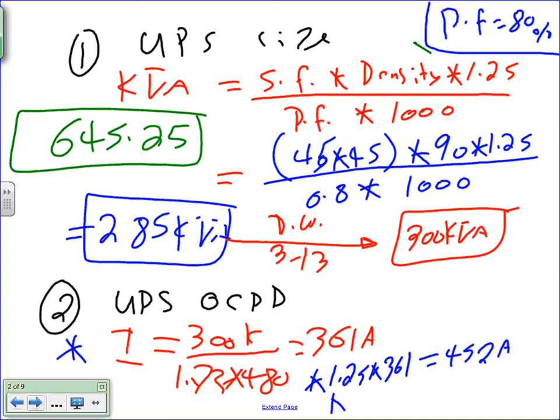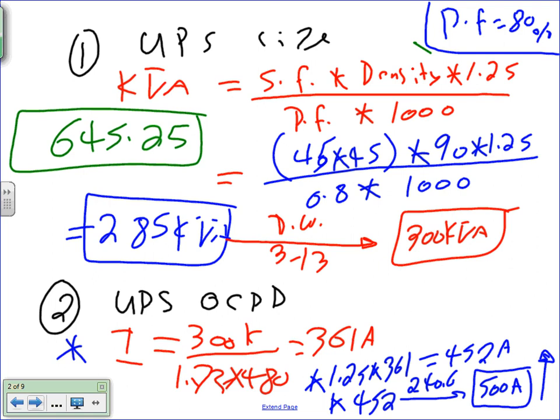And actually, the last one: if you take 452 amps, take it to 240.6 to find the standard, and that will get you 500 amp, and go up if it's not a standard. The last time around, you said it had to be less than or equal to the available sizes. Number 2 here, this or equal, not go up? Well, up to 800 amp. Remember that the ceiling is 800 amp. We can go up on the conductors. After that, you're absolutely right. After that, we have to match the overcurrent protection device to the conductor.